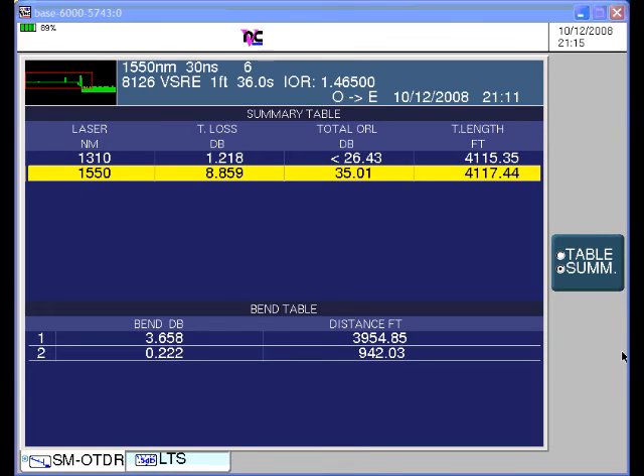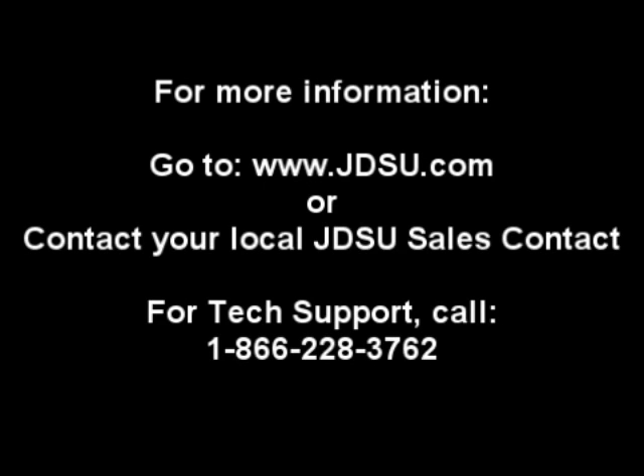There is another smaller bend that may or may not be of concern at 0.22 dB at about 942 feet. This concludes operation of the T-BERD 6000 in the fault locator mode.